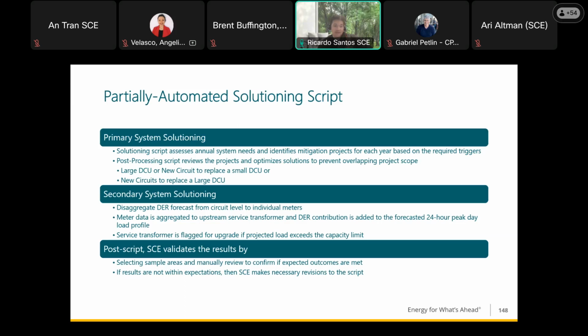So there's a pre-processing script that cuts over a 4 kV system load where load is exceeding equipment limitations. In cases where a 4 kV cutover need is identified, it will then transfer the projected load of the affected 4 kV circuits or substations to the nearest higher voltage system. After the 4 kV cutovers and eliminations are identified, the solutioning script then evaluates several criteria for other mitigation types.